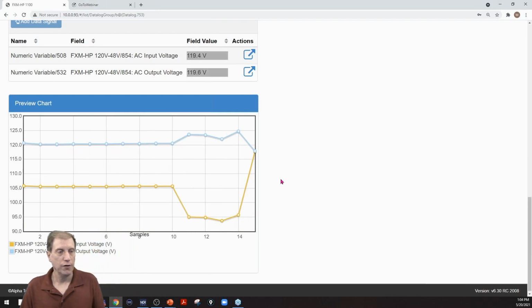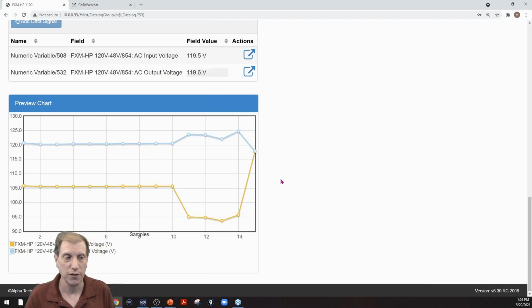So here we are, 119.5 volts, and now it stopped because that logic statement is now false. I'm now in between 110 and 130. So what does that really mean? What are these numbers I picked, 110, 130? Line is right in between 110 and 130. So that means I'm in buck, or I'm in boost mode, or I'm in inverter mode if I'm outside of this region. So anything that's not line mode is what I'm capturing here. That's why I picked those numbers.